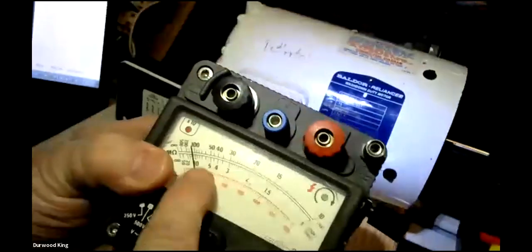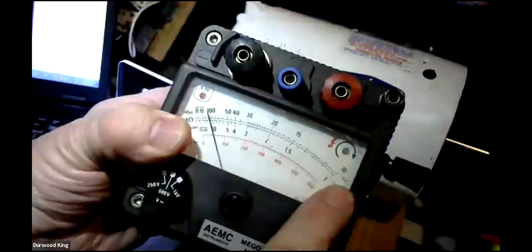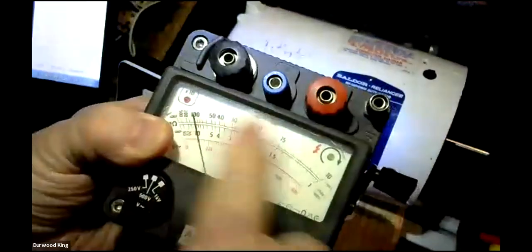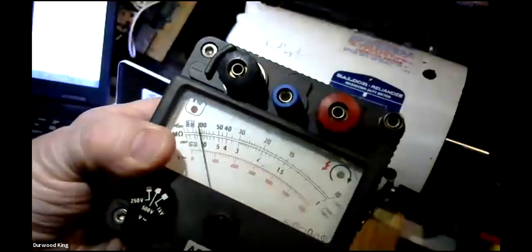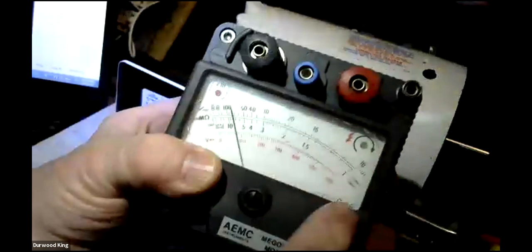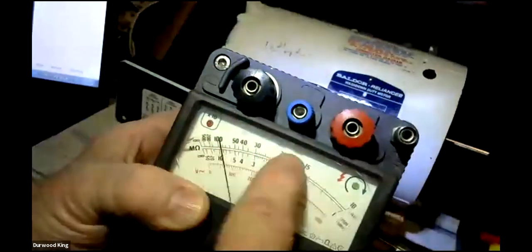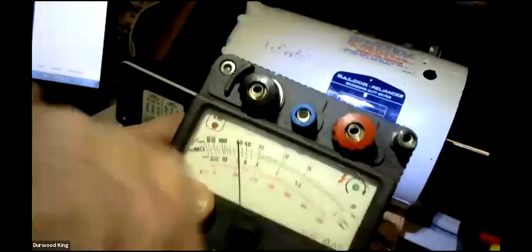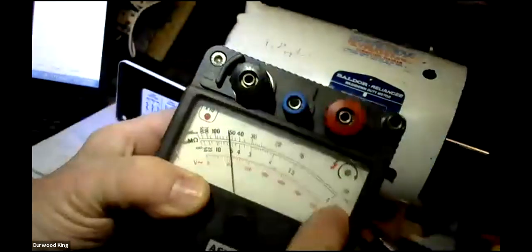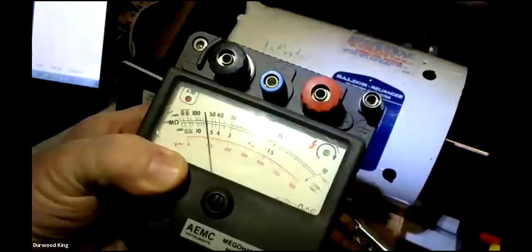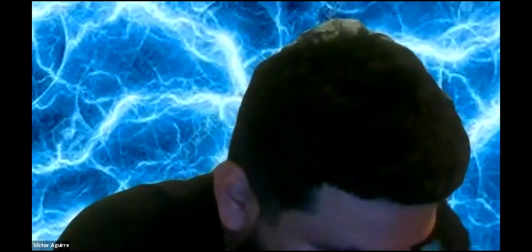Basically, when you crank it, if it swings way over, it's bad. If it stays over there, you're fine. Up here, you're way up in the high megaohms. So if you're over 1, you're fine. That meter tells you if you're in that range, you're okay. If it swings over hard, way over to here, it's bad. So that's basically it.